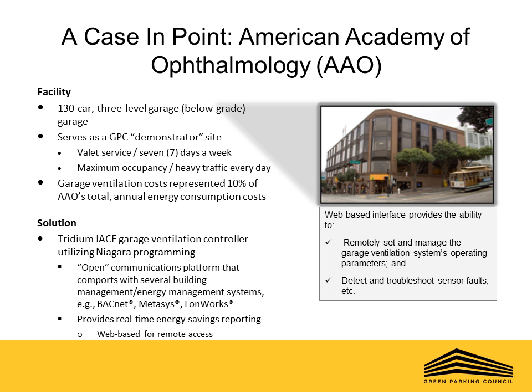Also let him know that the fans that were blowing people's hairdo as they walked by the vents wasn't happening anymore. In fact, a few people complained that the garage fans were not operating any longer. But in fact, they were actually operating at a really steady 25%. And as necessary, when the sensors detected the 25 parts per million of CO, they would ramp up slowly, they would clear the garage, and then they would ramp themselves back down.